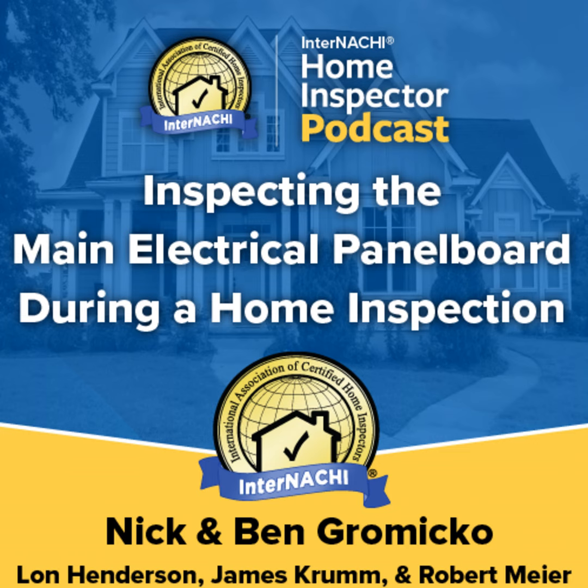The home inspector should know that the IRC and NEC provide an exception to the general rule for overcurrent protection ratings of breakers and the connected wire sizes. And knowing that exception and applying it will help home inspectors do better inspections. Read more about inspecting oversized AC breakers by visiting www.nachi.org/inspect-oversized-air-conditioning-small-gauge-wires.